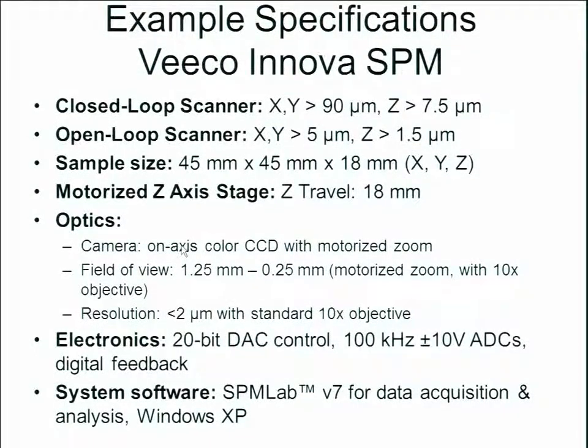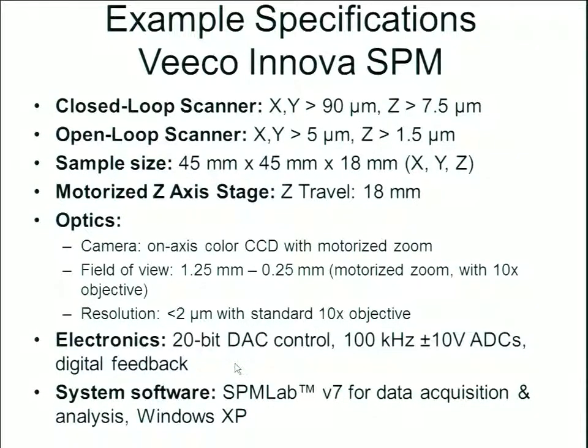As far as specifications, you typically have a scan range near 100 microns. Sample sizes depend on the manufacturer but are around 50 by 50 by 20 millimeters. The optics typically include a CCD-mounted optical microscope. There are also different types of software to interact with the tool.